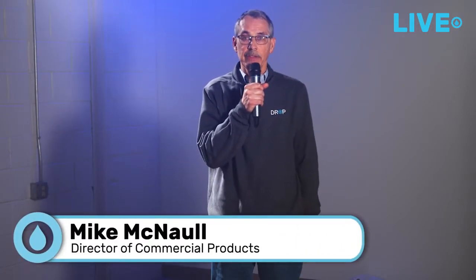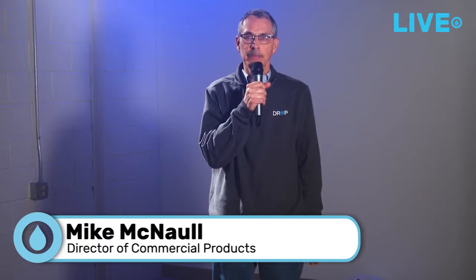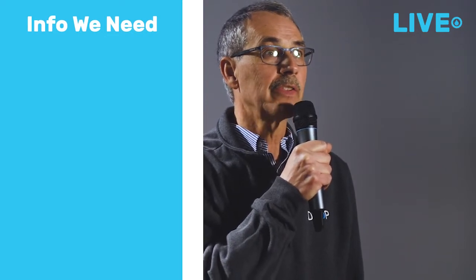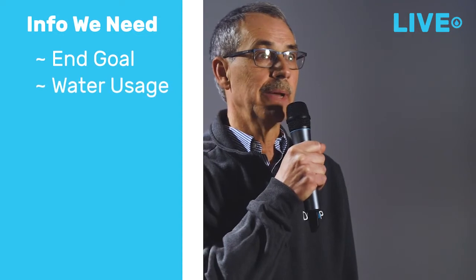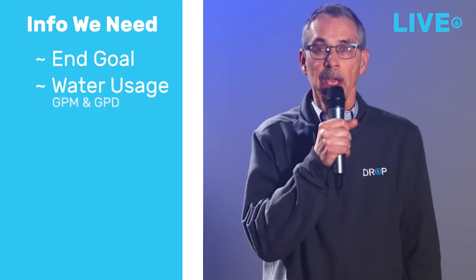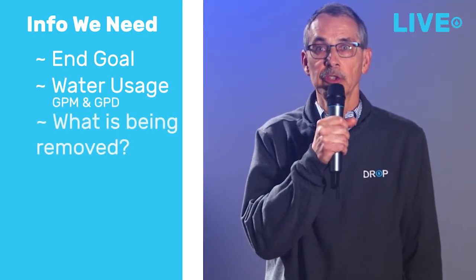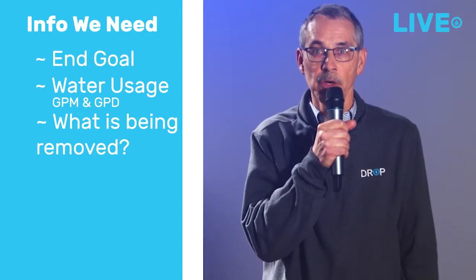Greetings. We are now going to talk about pain-free sizing your new commercial water treatment system. We want to make this as easy as possible and make sure that the correct equipment is installed, so we need some information going in. We need to know what's the end goal, how much water are they using, both in gallons per minute and gallons per day, and what are the characteristics of the water that your customer wants to have removed.